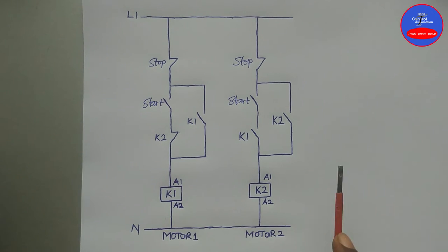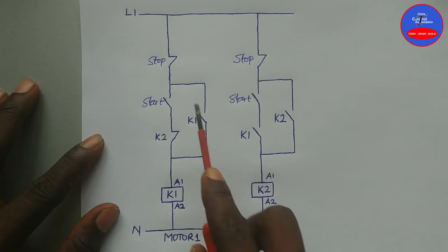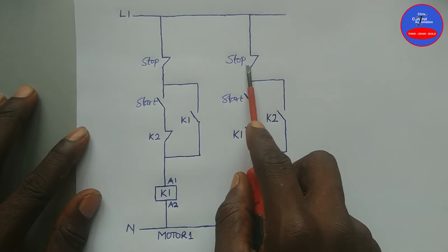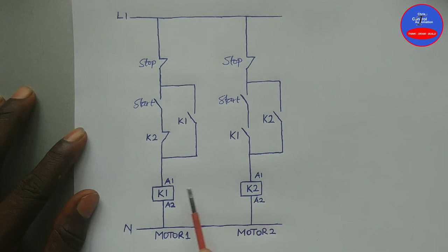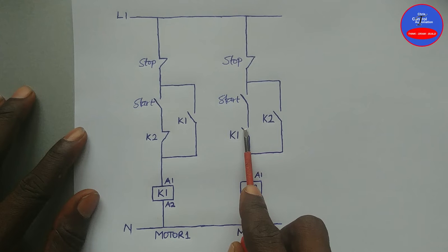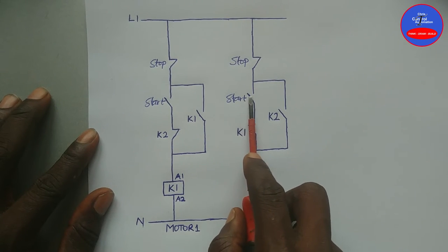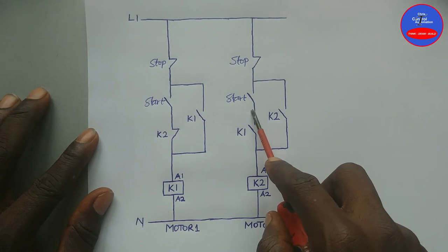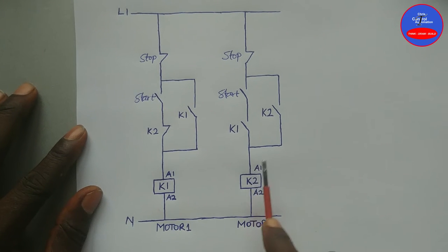As K2 is energized, this contact is open. Now we have two motors running: Motor 1 and Motor 2. We can de-energize each contactor using their stop buttons. When we press on the stop button of Contactor 2 it will de-energize, but because Contactor 1 is still energized this contact is closed. Therefore when I press on the start button again, current can flow through this close contact, through this close contact, and then through the close contact on K1 to re-energize K2.